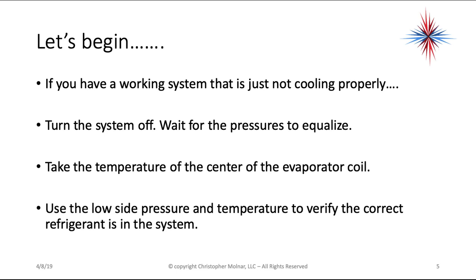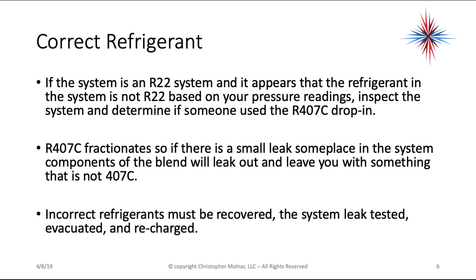This first check is extremely important, especially with newer refrigerants. Turn the system off and wait for the pressures to equalize — so you have your gauges on the system and your pressures are going to equalize. Take the temperature of the center of the evaporator coil. Use the low side pressure and temperature to verify that the correct refrigerant is in the system. This gets extremely important when talking about blends. If the system is an R22 system and the refrigerant appears not to be R22 based on your pressure readings, inspect the system and determine if someone used the R407C drop-in. R407C fractionates, so if there's a small leak, the components of the blend will leak out at different rates and leave you with something that is not R407C.